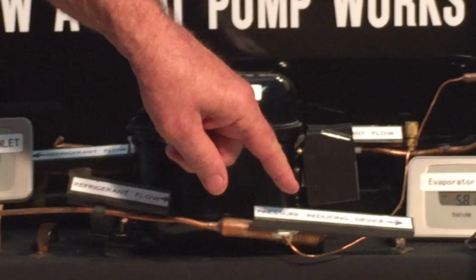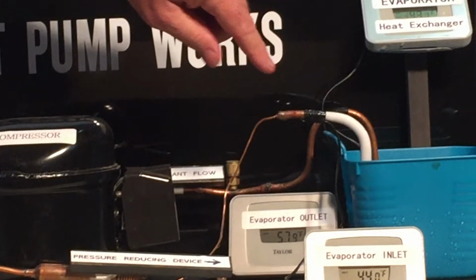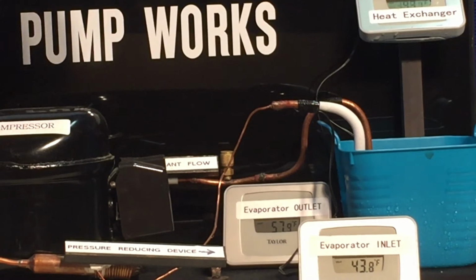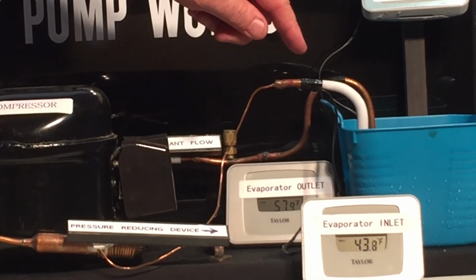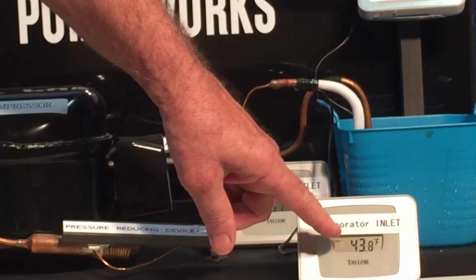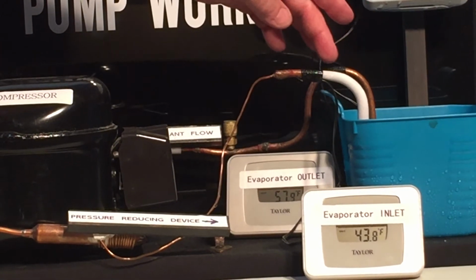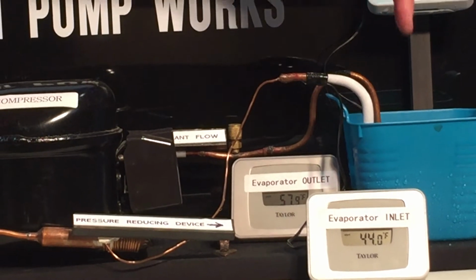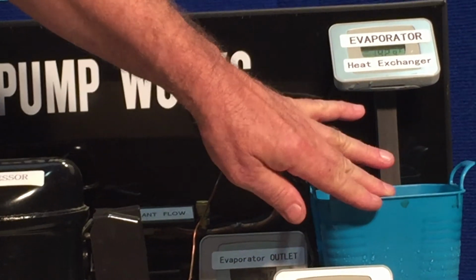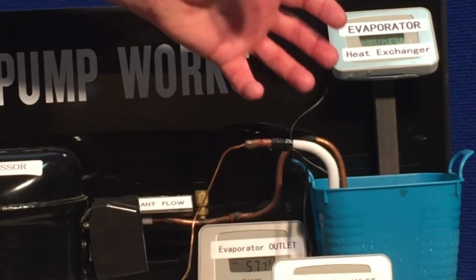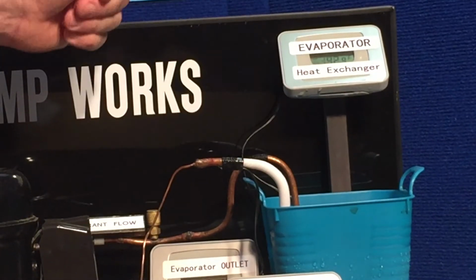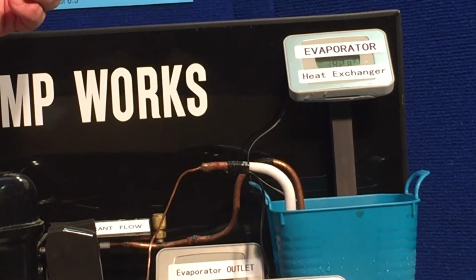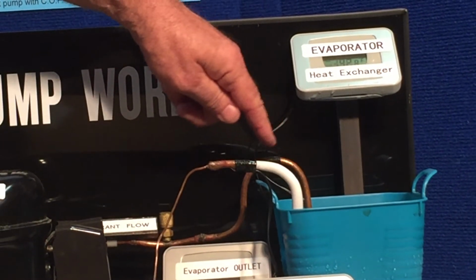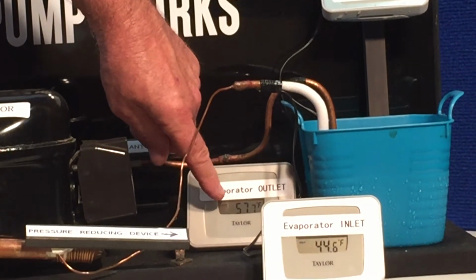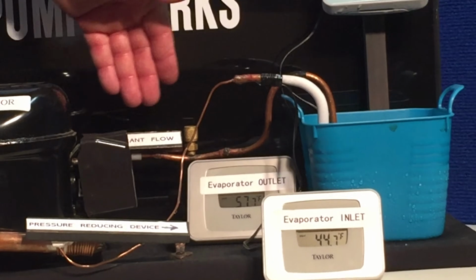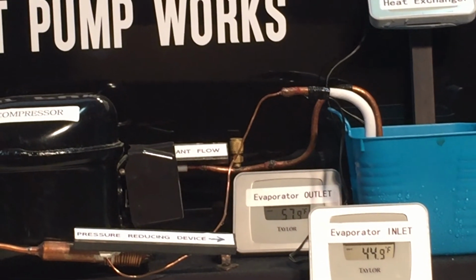The refrigerant flows down this line, and through the capillary it does the opposite of what the compressor does. It relieves that pressure, and you can see by relieving the pressure the temperature has dropped significantly. The thermometer says we're down to about 44 degrees, and you can even see frost accumulating on this tubing. The refrigerant goes through the coil of tubing in the evaporative heat exchanger, and it is absorbing heat out of the water, making that colder.